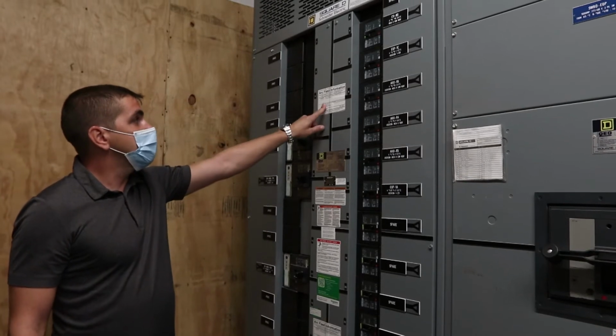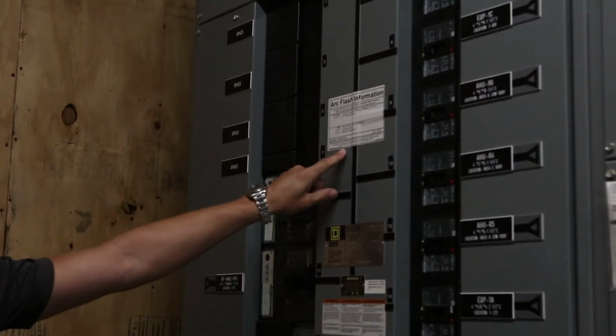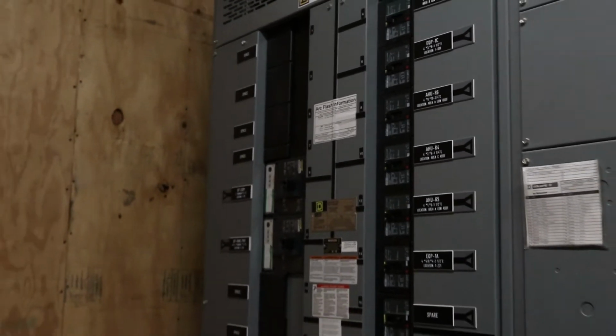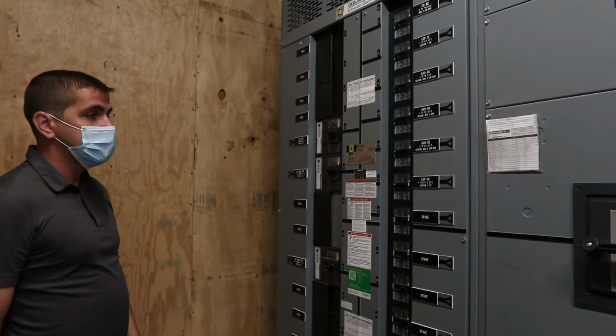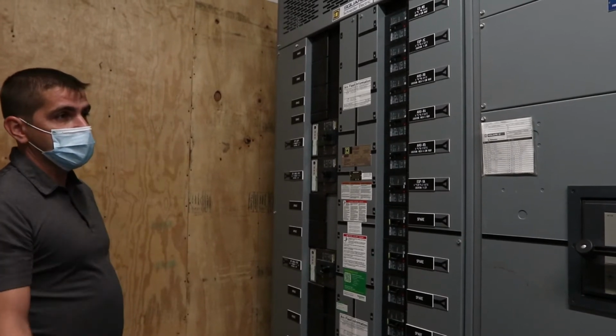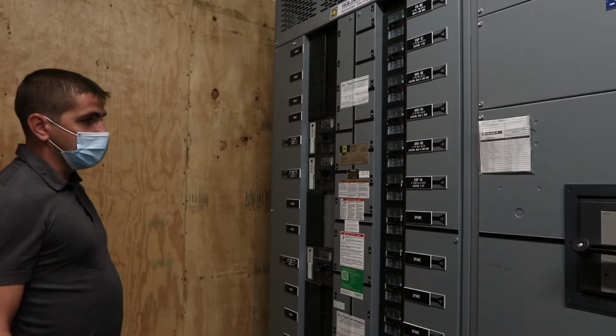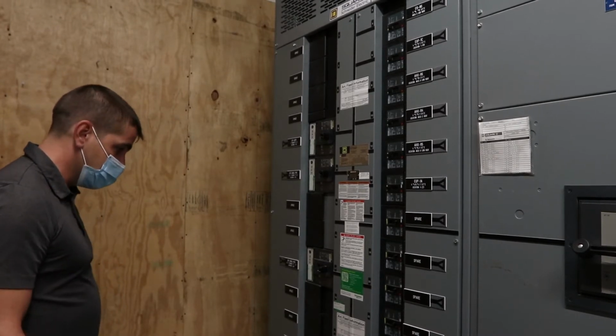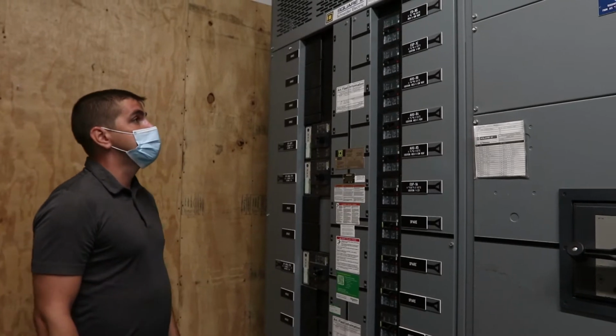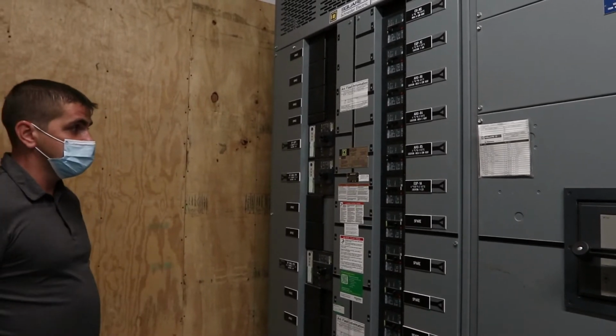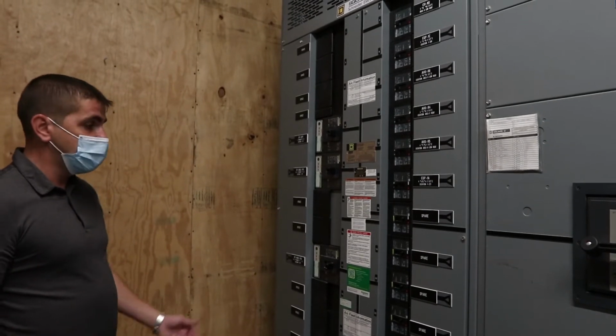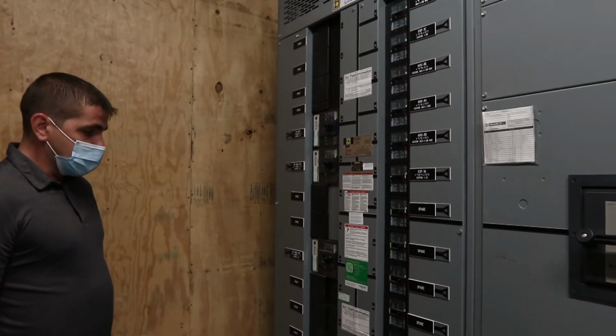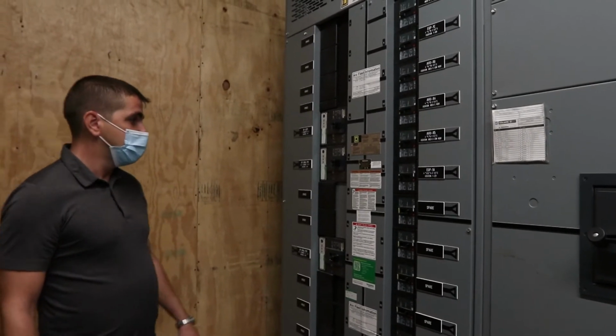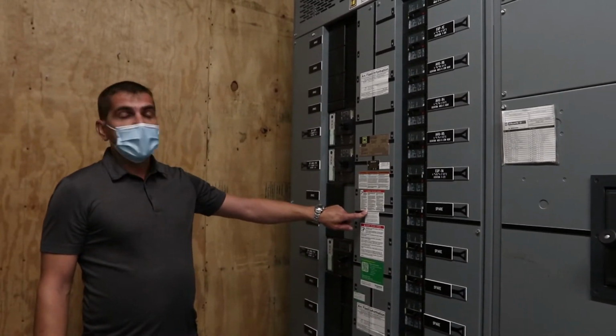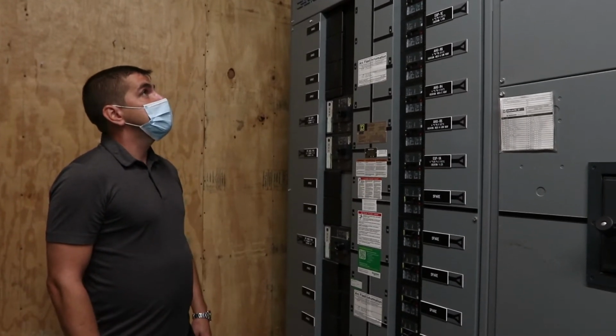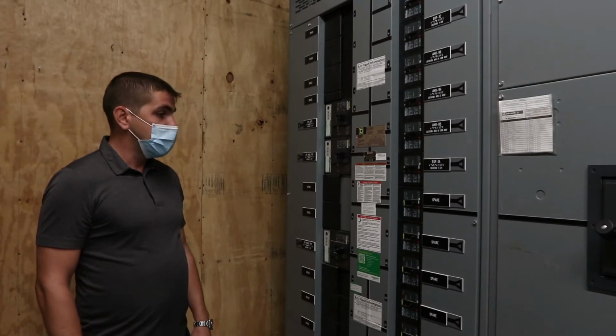Also, you see all of the arc flash information, which says any service of the equipment should not be performed while the equipment is energized. If you need to perform any work, the main breaker has to be disconnected. Then the front cover can be removed, and the equipment can be serviced. In the unlikely event that the equipment has to be serviced while energized, you have to follow the safety instructions, and working with all of the protective gear has to be noted. The facility has its own procedure for maintaining equipment while it's energized. Other than that, there is not much maintenance required.